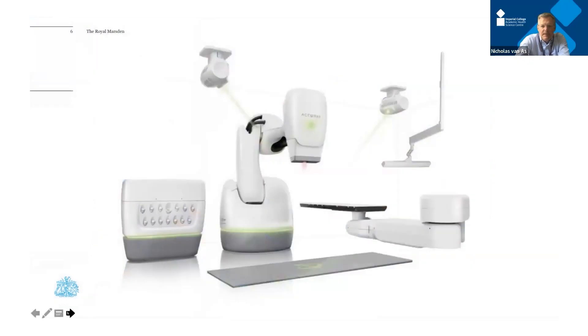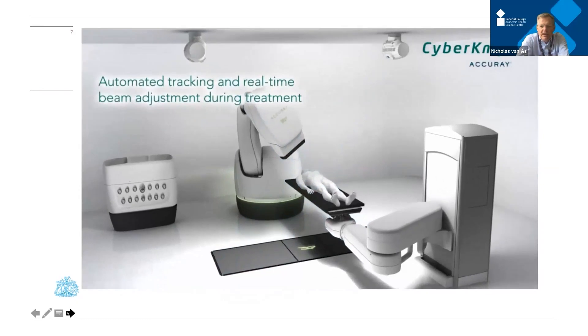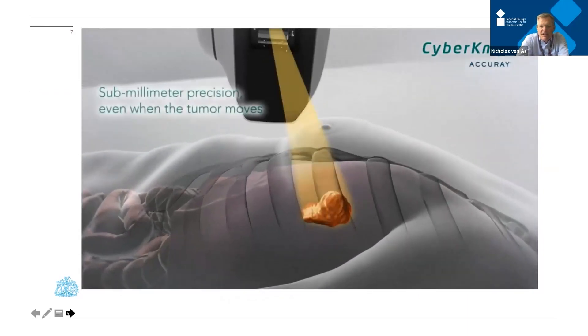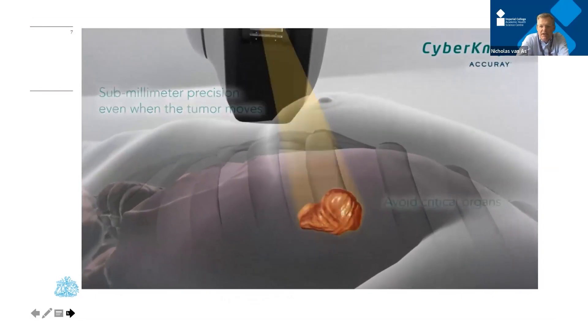This is an example of a CyberKnife, which we use at the Christie. It differs from a standard radiotherapy machine in that the linear accelerator is mounted on a robot and can move in all different planes, delivering very fine beams of radiotherapy extremely accurately. It has the ability to track a target as it moves, using x-ray machines on the roof and a sensor on the floor to take real-time images.